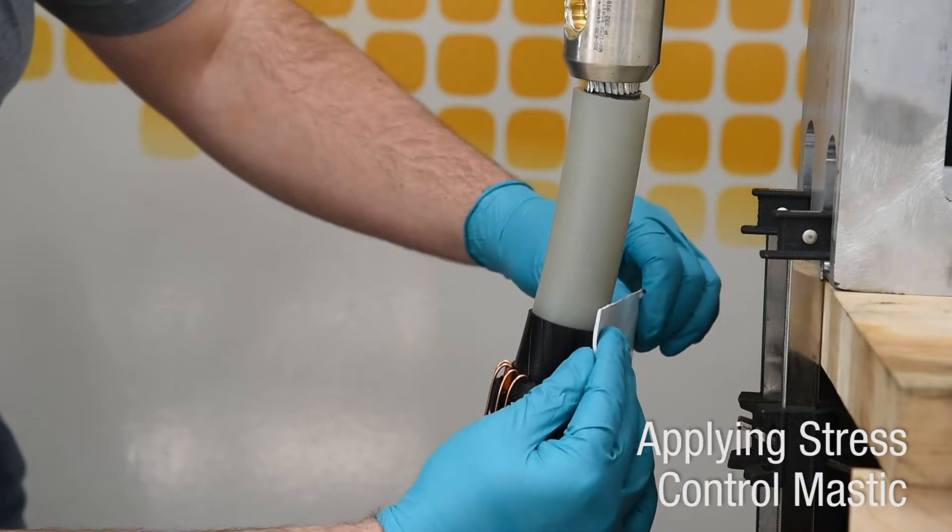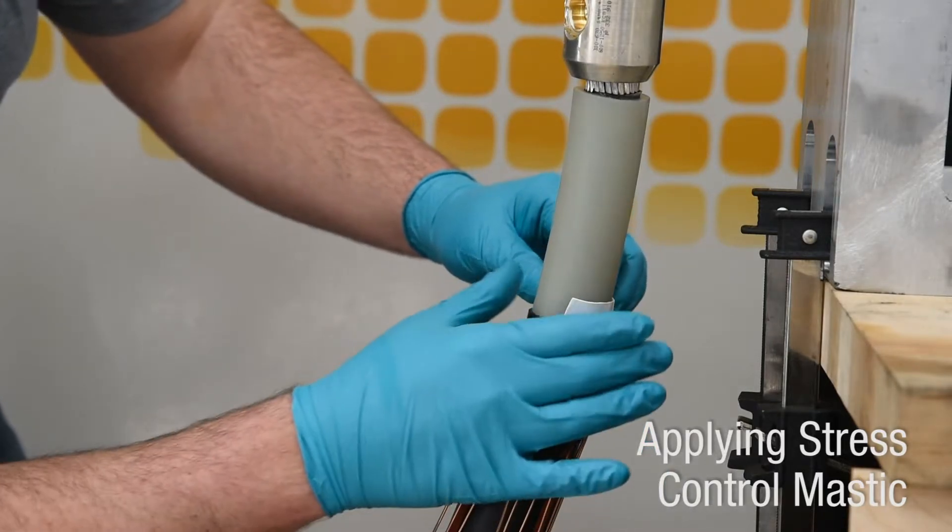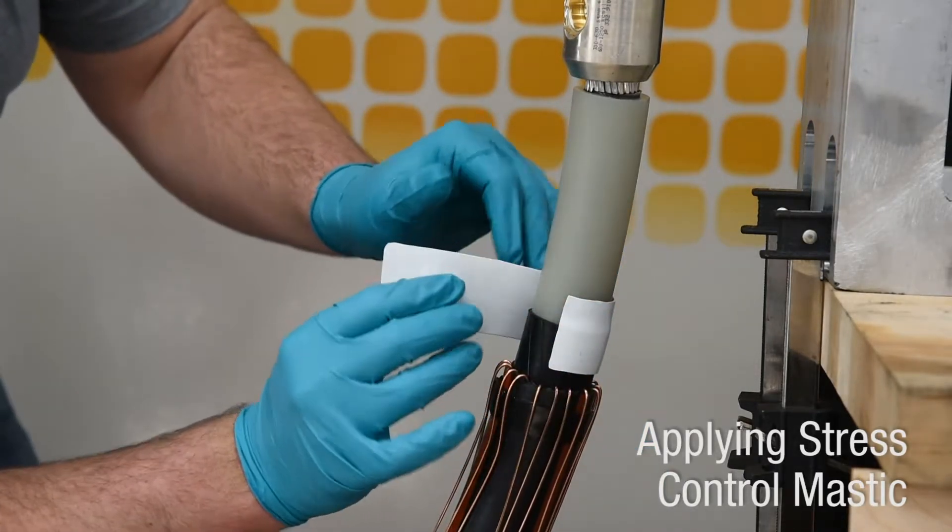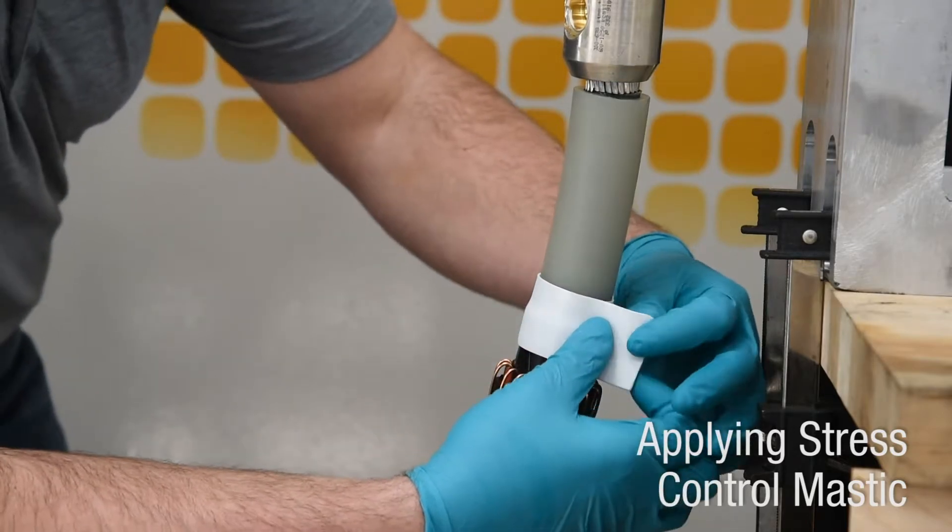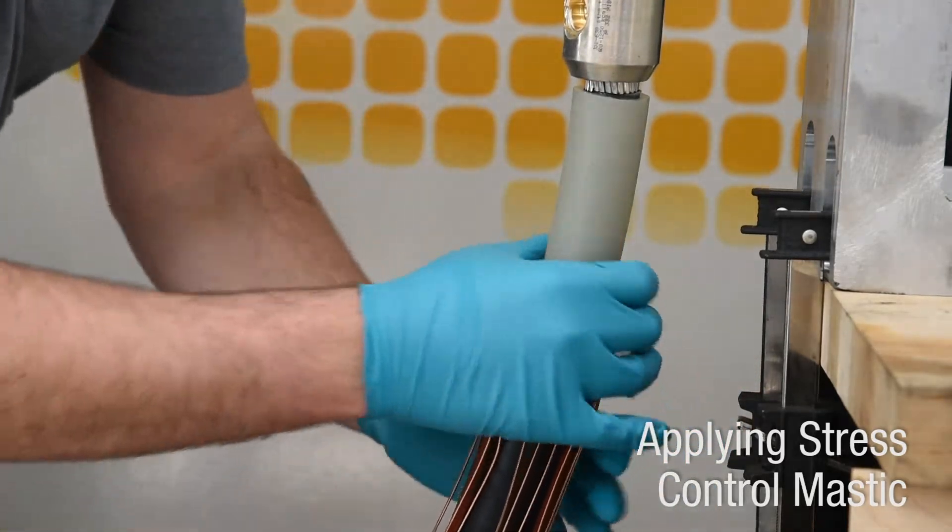Apply supplied stress control mastic centered over edge of semiconductor shield cutback. Apply the mastic with light tension so it slightly stretches and completely wraps the cable.